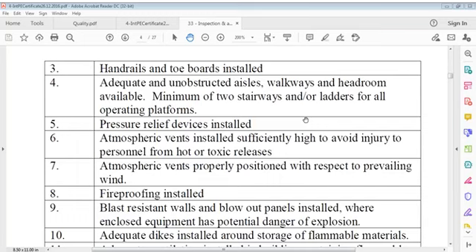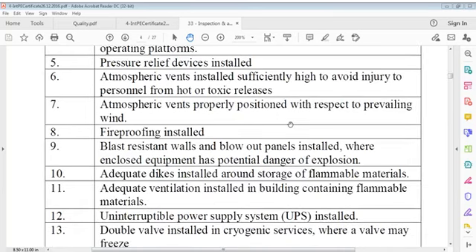Also there may be many devices where pressure relief devices are installed, on many vessels or equipment or other areas where pressure is involved, to avoid injury to personnel from hot or toxic releases. Atmospheric vents properly positioned with respect to prevailing winds. Fireproofing installed, blast resistant walls and blowout panels installed where enclosed equipment has potential danger of explosion, where explosion can happen anytime. So we have to protect that with blast resistant construction. Adequate dikes installed.